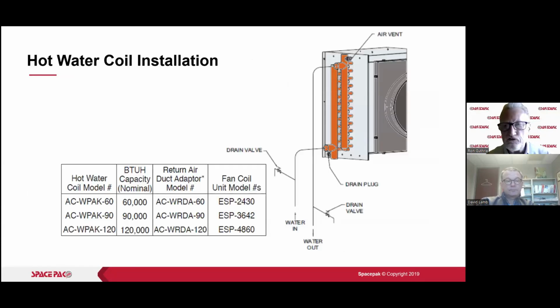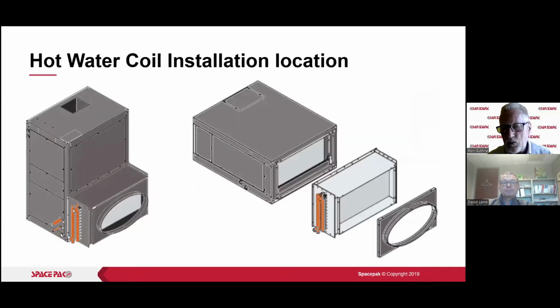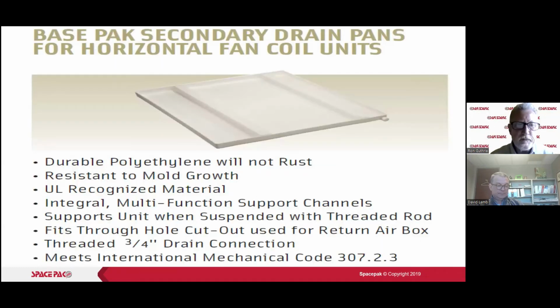All right, and those go, I mean, it's just typical piping. Of course, the water out's going to be on top. That's where your air vent's going to be. And the way that they mount onto the units is we remove the unit flange on the return side of the unit, and this heater mounts to the unit, and then the flange mounts to the coil, the hot water coil. Okay, so it's pretty simple.